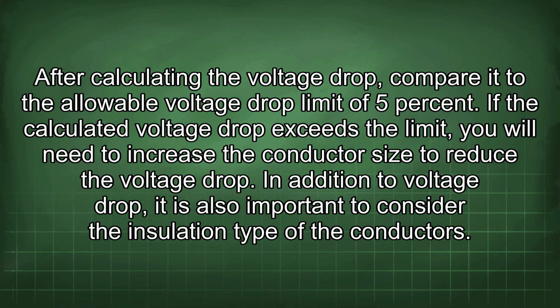After calculating the voltage drop, compare it to the allowable voltage drop limit of 5%. If the calculated voltage drop exceeds the limit, you will need to increase the conductor size to reduce the voltage drop. In addition to voltage drop, it is also important to consider the insulation type of the conductors.